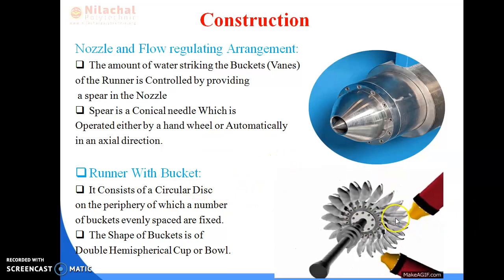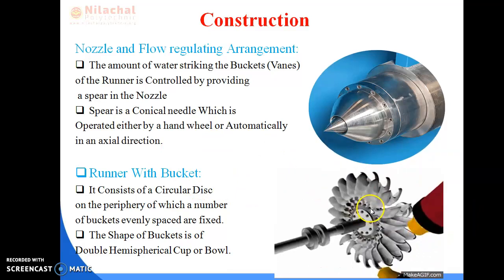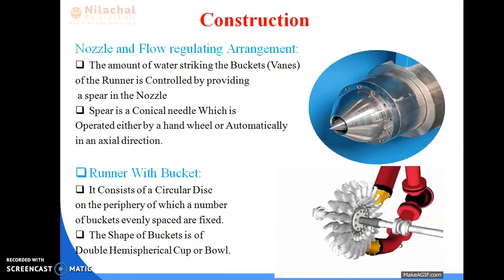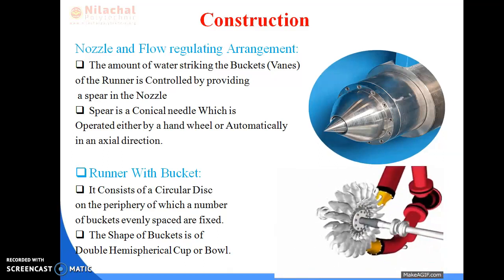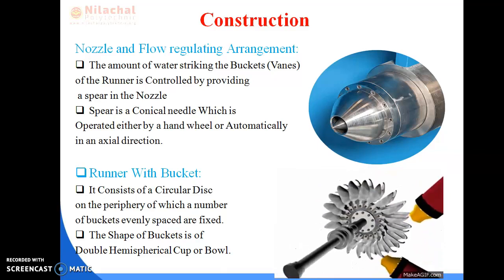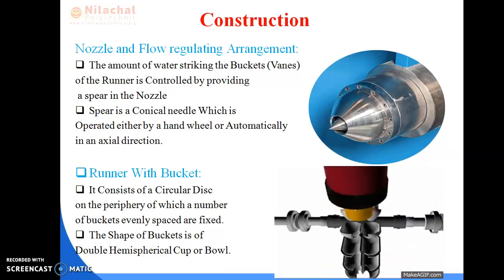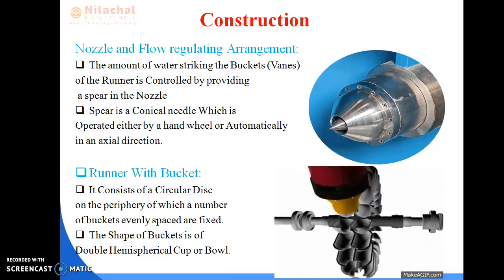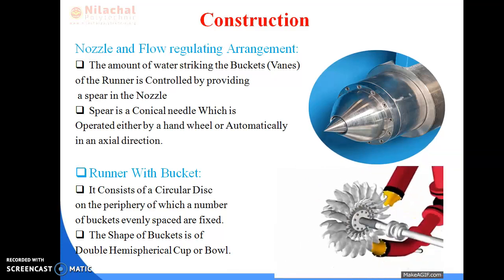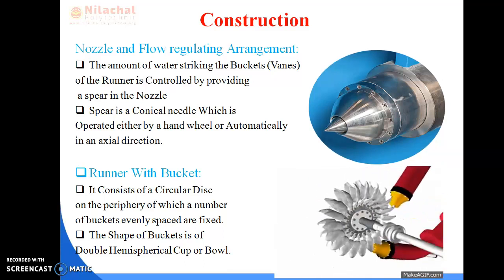The next part is the runner with bucket. As shown in the figure, the buckets are fixed to the runner, and the runner is fixed to the shaft. In the case of an impulse turbine, the blades are known as buckets. The bucket consists of two hemispherical cups attached to each other at a point known as the splitter. The splitter divides the water into two parts when the water strikes the bucket, causing the flow of water through the hemispherical cups and then out of the bucket.